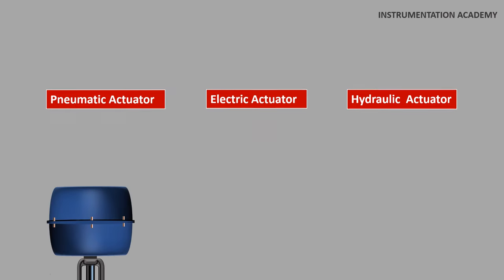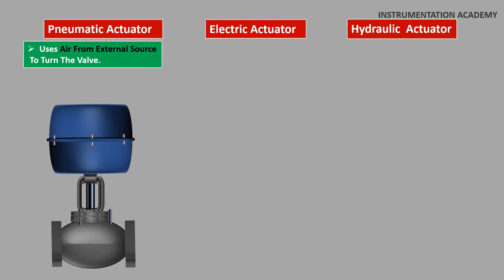Pneumatic actuator use an air or gas signal from an external source to turn the valve. Pneumatic actuators are the most commonly used actuator for valves in the process and oil industries. In this type the compressed air is applied either on a diaphragm or on a piston which in turn moves the valve stem.